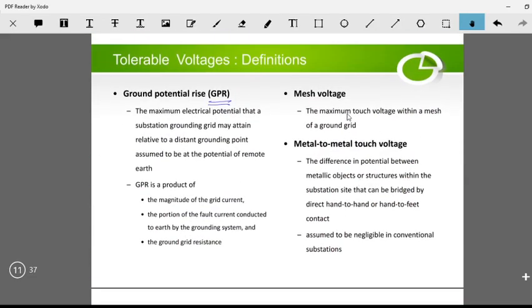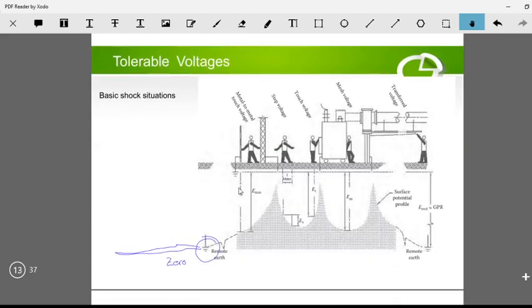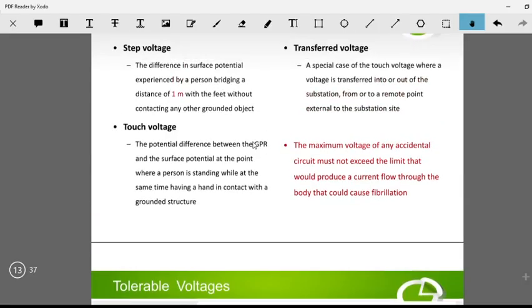There's also the metal-to-metal touch voltage. In this diagram there are two metal structures in the substation, both connected to the grounding grid. If somebody touches both, there is a potential between these two points, which is called the metal-to-metal touch voltage.